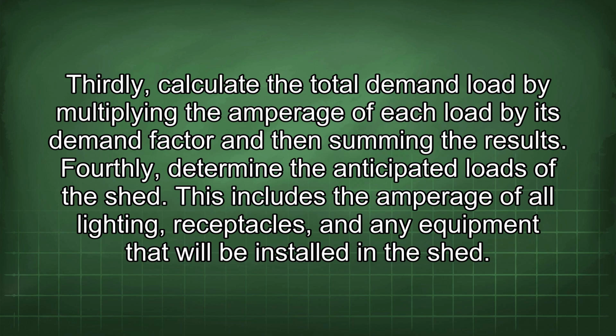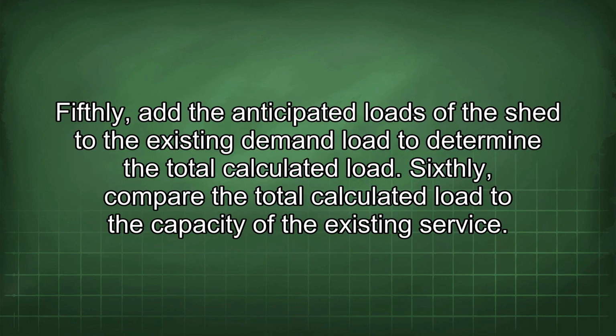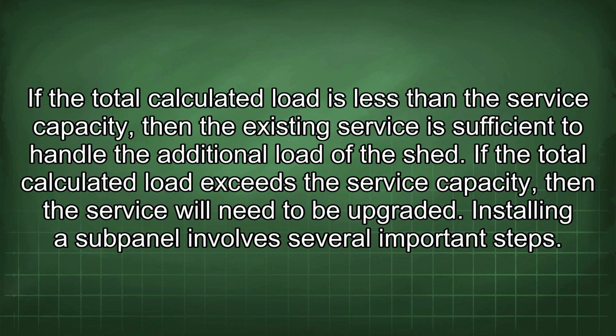Fourthly, determine the anticipated loads of the shed. This includes the amperage of all lighting, receptacles, and any equipment that will be installed in the shed. Fifthly, add the anticipated loads of the shed to the existing demand load to determine the total calculated load. Sixthly, compare the total calculated load to the capacity of the existing service. If the total calculated load is less than the service capacity, then the existing service is sufficient to handle the additional load of the shed. If the total calculated load exceeds the service capacity, then the service will need to be upgraded.